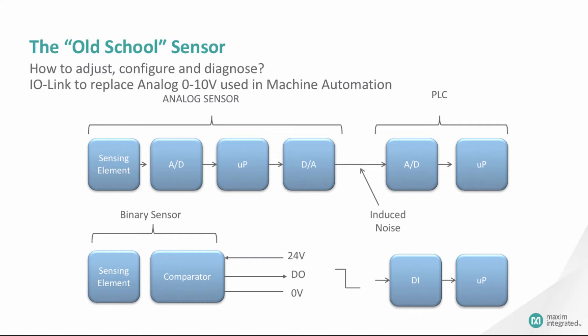As technology advanced, sensor manufacturers found they could integrate more functionality into their sensors, eliminating some of these problems. Binary sensors were created, defined and standardized in IEC 60947-5-2. The standard defines binary sensors as a sensing element — for example, inductive, capacitive, ultrasonic, photoelectric, etc. — with a semiconductor switching element. Per the standard, switching elements can be defined as normally open, normally closed, changeover, or user programmable.